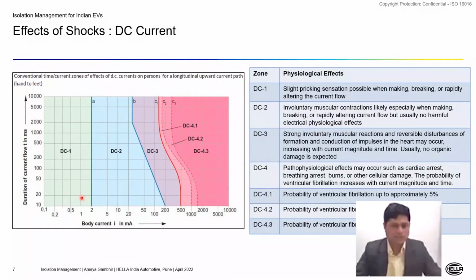But to be on the safer side, we always consider that any DC current more than 10 milliamps should be avoided in the IMD. The next zones are probably similar - as you go towards more current on the right side of the x-axis, there is a possibility of life-threatening hazard.